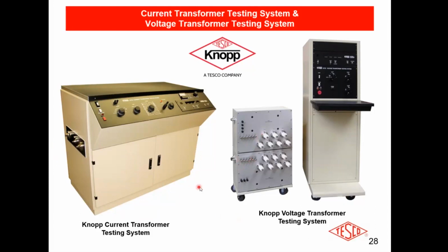And you compare what the system sent through the loading transformer to the precision transformer and the transformer under test. It's pretty basic. Whatever you saw here, you compare that to what you saw at the instrument under test. You consider this to be perfect because it's a precision transformer, and however much different the instrument under test is, that's your accuracy. If on the current side you only saw 99.2% of what the precision transformer saw, that's how accurate you would be. And the instrument transformers, by the by, are usually much more accurate than that. Same thing with the voltage transformers. So again, pretty simple: loading transformer, precision transformer, and transformer under test.